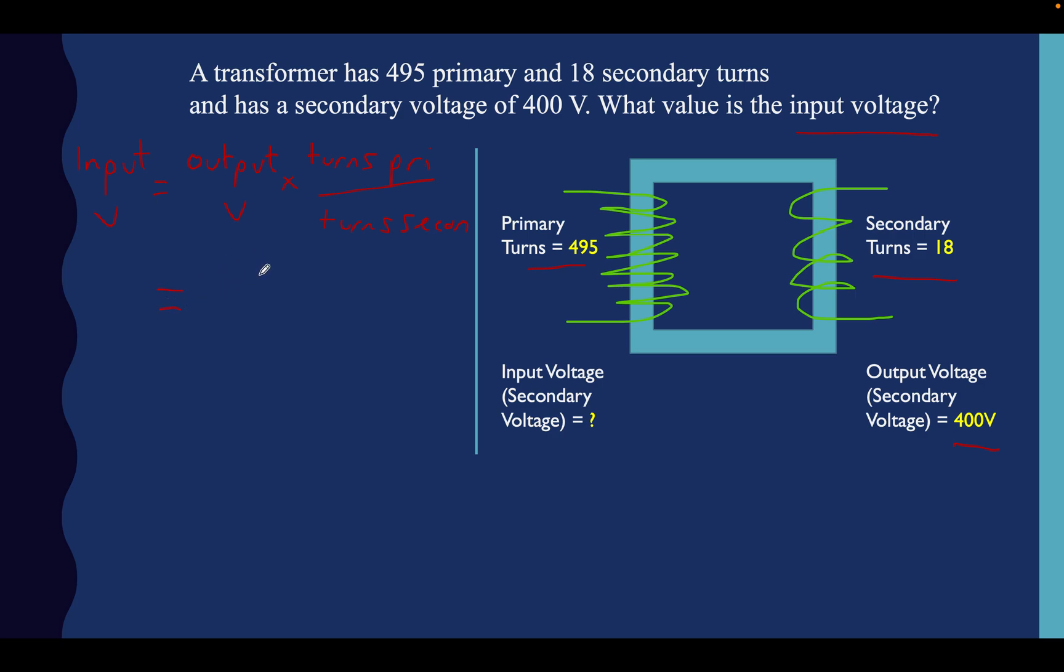So let's do that below here now. First of all, let's do turns on primary, turns on secondary, and multiply it by 400. So we're going to have 400 volts because that's our output voltage there. And we're going to multiply it by 495, which is our primary turns on the top line, divide it by 18, which is our secondary turns on this side.